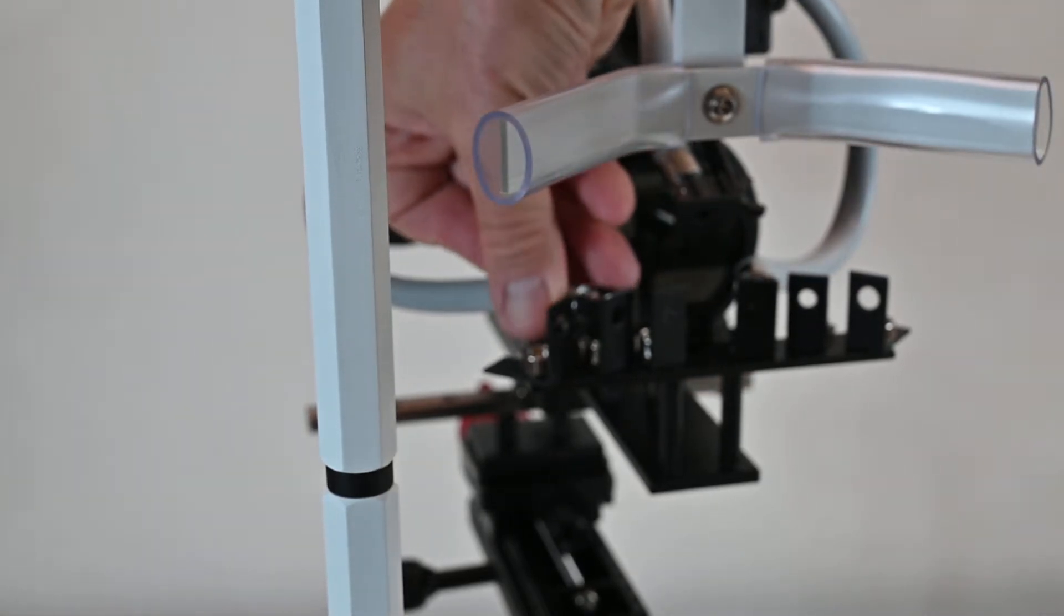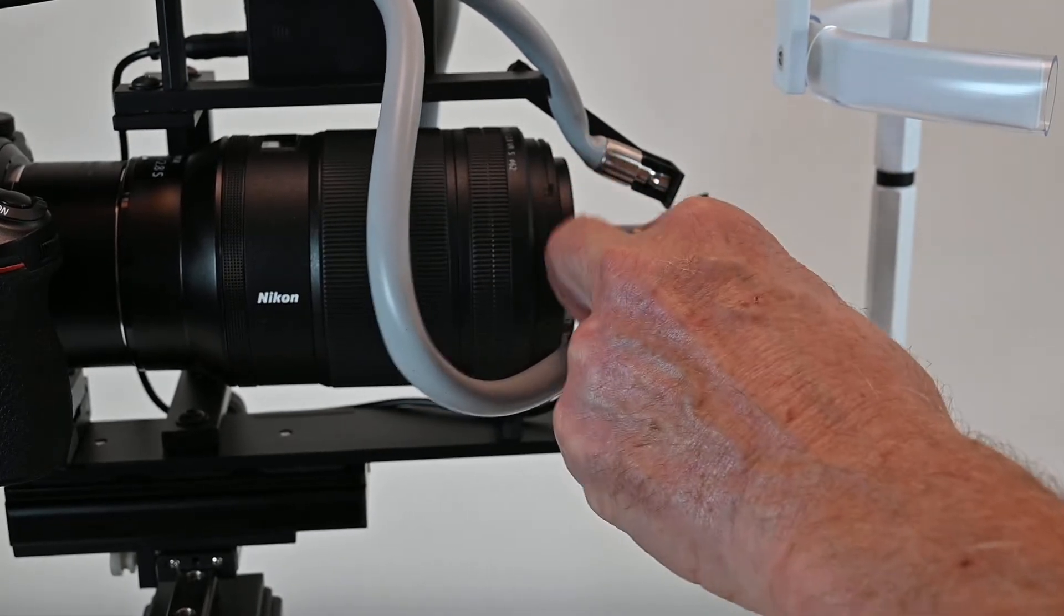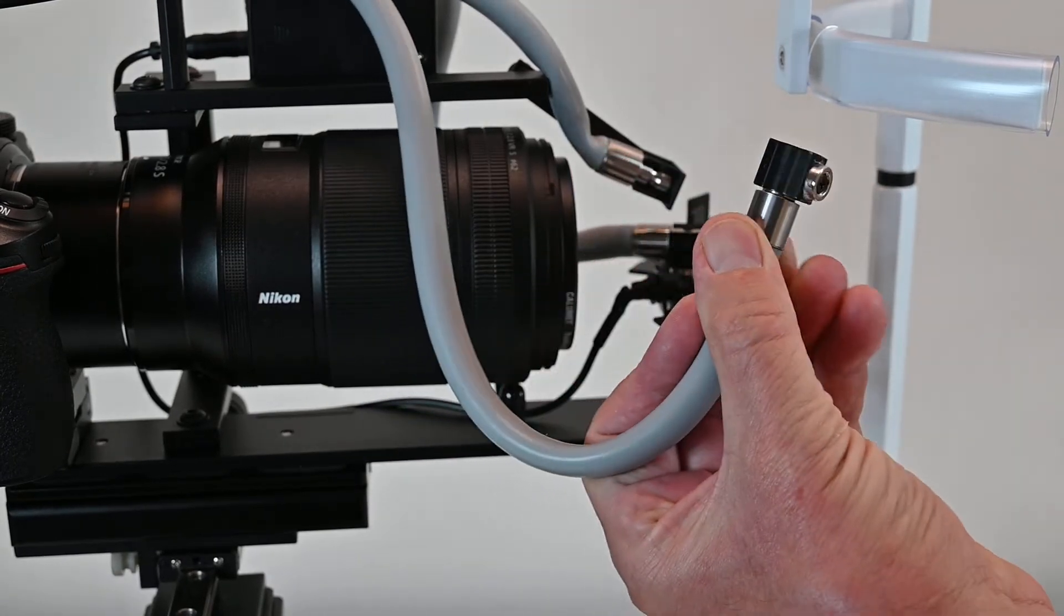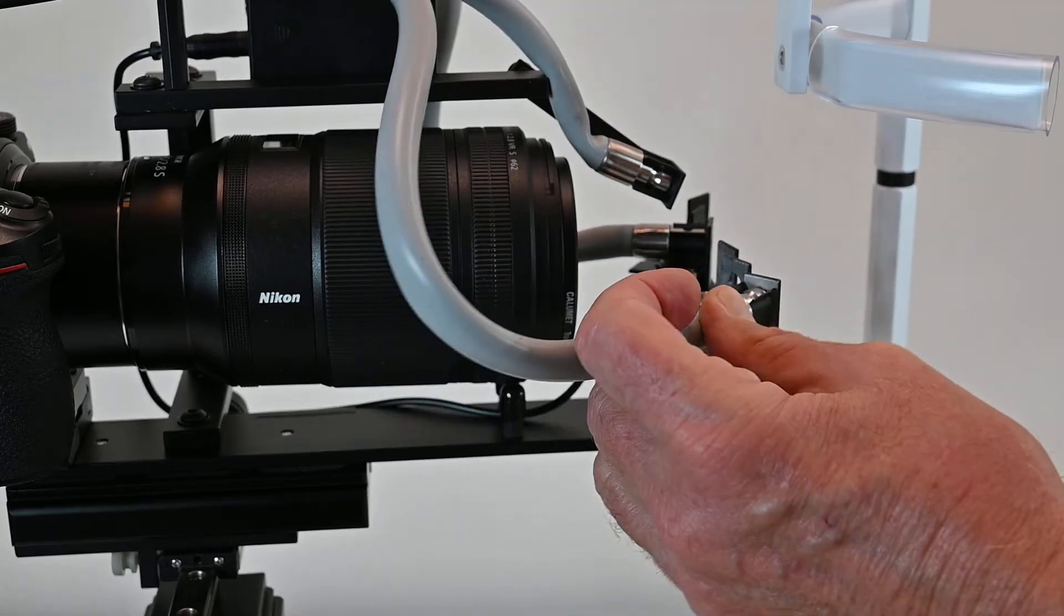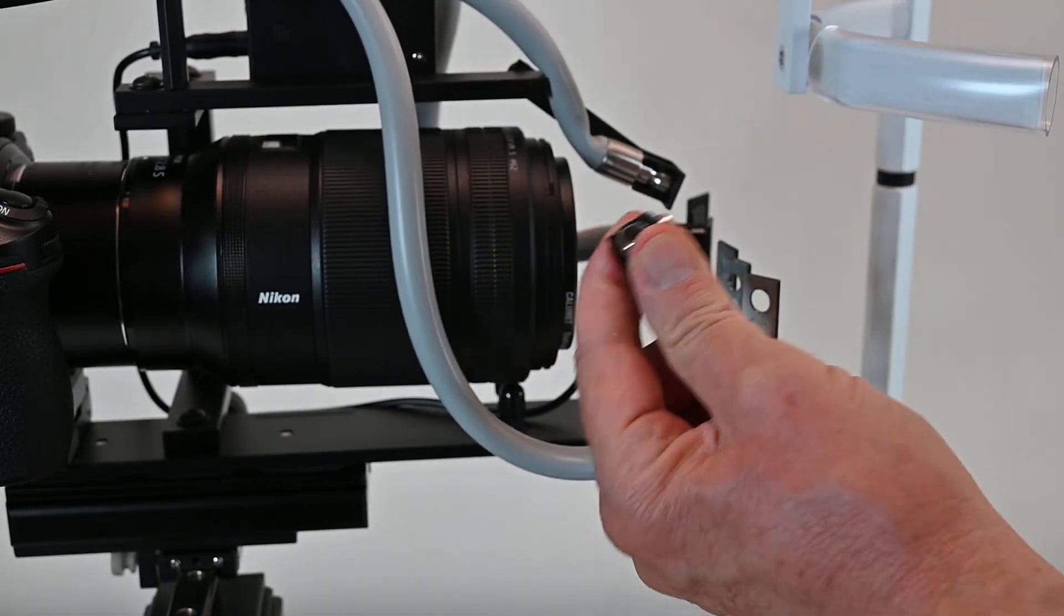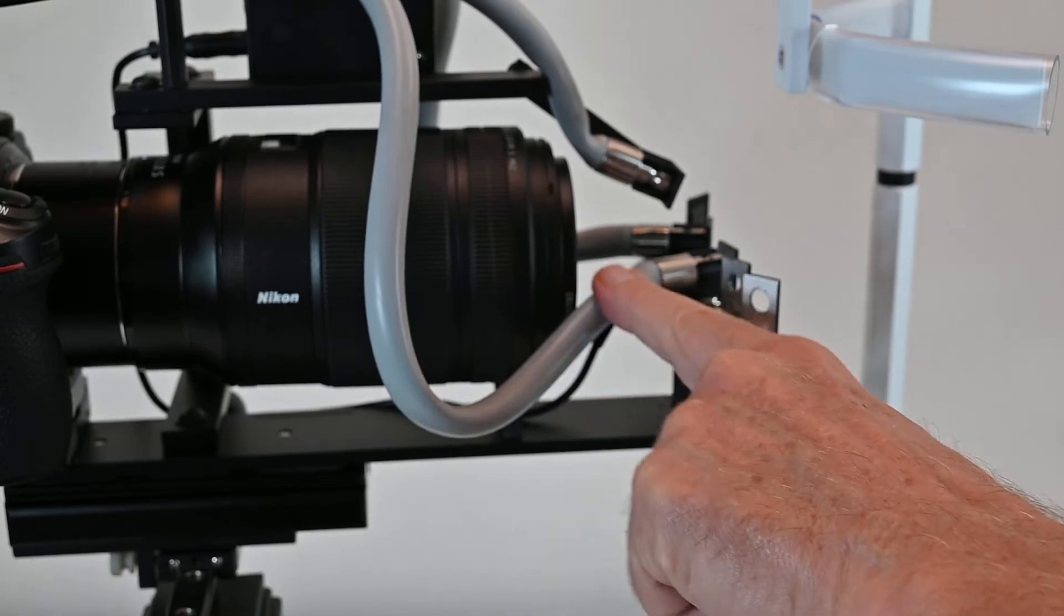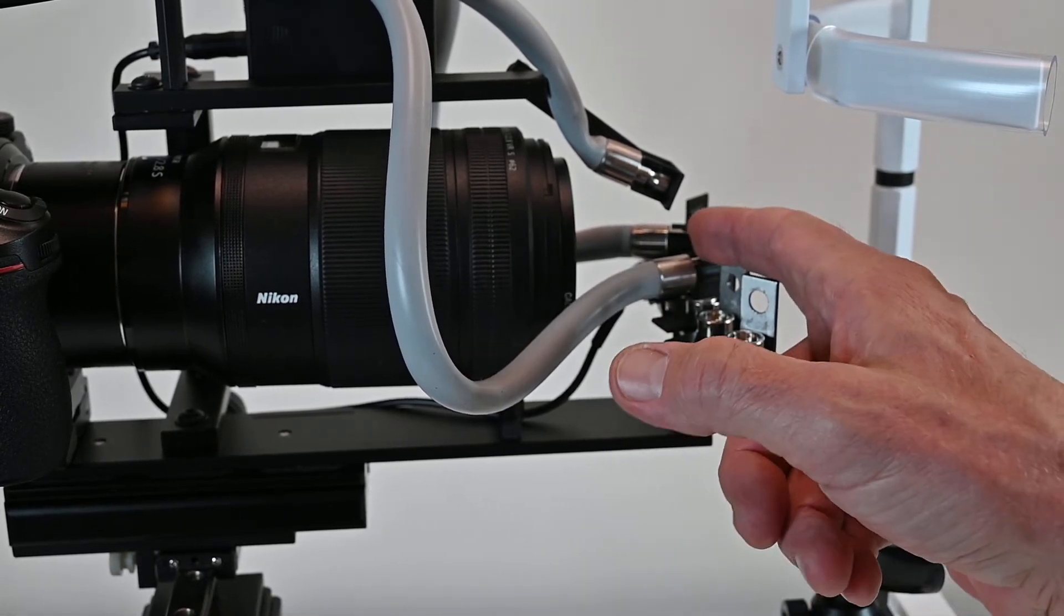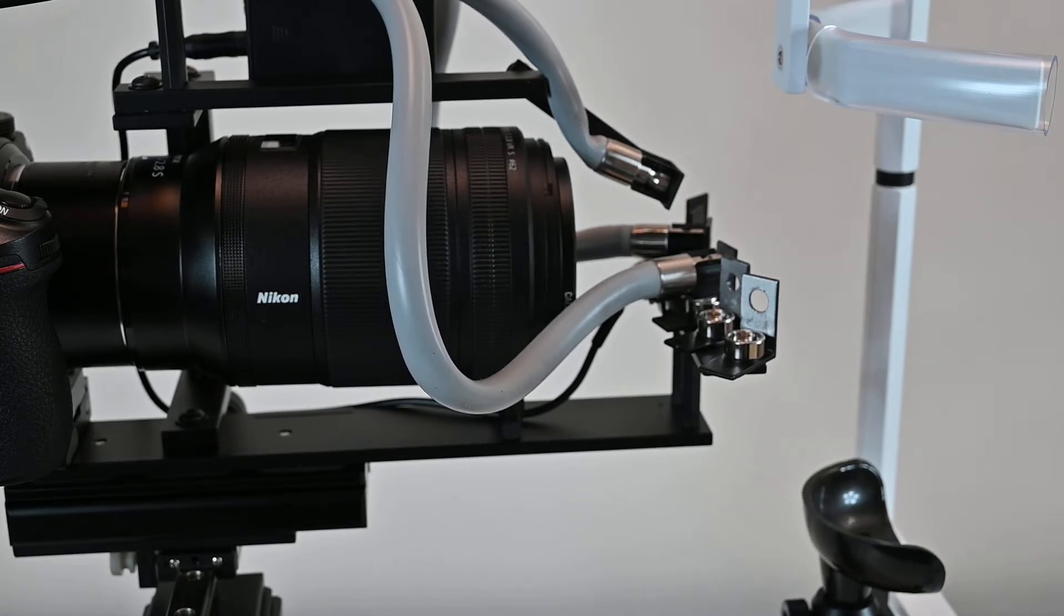To change this lighting angle, I just tilt it down like that, lift it up, and then I put that magnet disc into a different cup. Let's say about 45 degrees. I'll put it in there, and then when it rests fully seated it will be very firmly in place. There's like no wiggle room, and that's exactly 45 degrees. It's a lot faster than dealing with three wing nuts on each side. When the lens cap is out, you can actually get it into the 15 degree socket quite easily, and that's perfect for center lighting. If you want the reflection to fall entirely in the pupil at the center, use 15 degrees lateral side lighting.